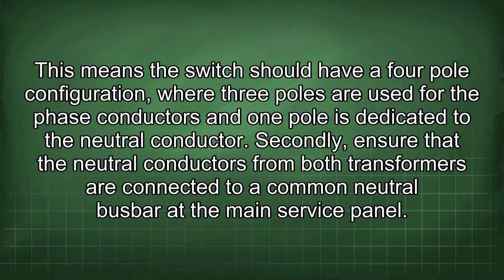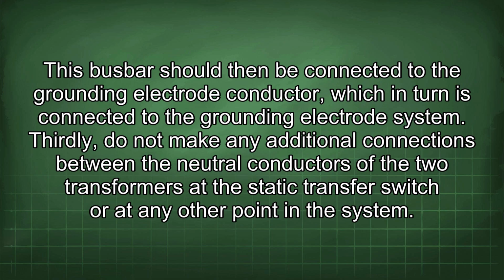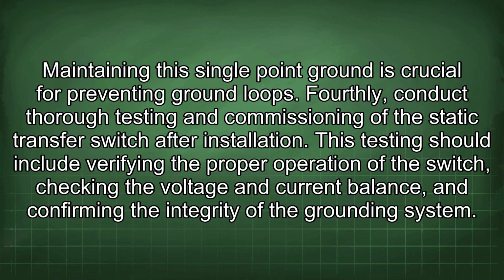Secondly, ensure that the neutral conductors from both transformers are connected to a common neutral busbar at the main service panel. This busbar should then be connected to the grounding electrode conductor, which in turn is connected to the grounding electrode system. Thirdly, do not make any additional connections between the neutral conductors of the two transformers at the static transfer switch or at any other point in the system. Maintaining this single-point ground is crucial for preventing ground loops.